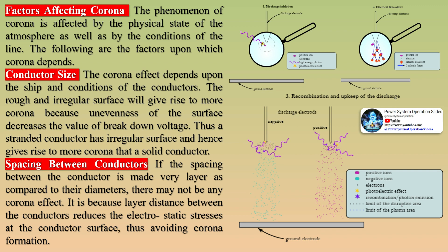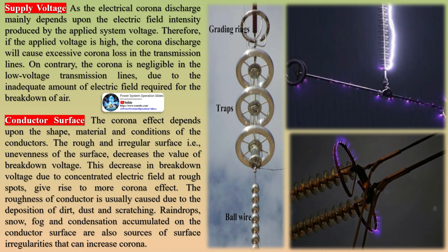Factors affecting corona: the phenomenon of corona is affected by the physical state of the atmosphere as well as by the conditions of the line. Regarding conductor size, the corona effect depends upon the shape and conditions of the conductors. A rough and irregular surface gives rise to more corona because unevenness of the surface decreases the value of breakdown voltage. A stranded conductor has an irregular surface and hence gives rise to more corona than a solid conductor. Regarding spacing between conductors, if the spacing is made very large compared to their diameters, there may not be any corona effect, because larger distance reduces the electrostatic stress at the conductor's surface.